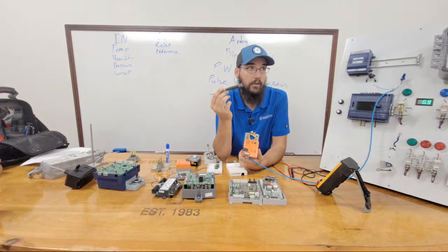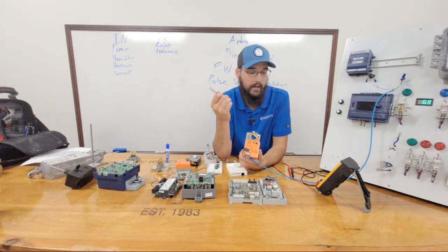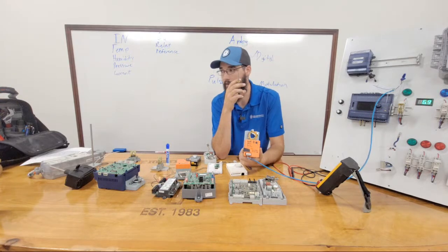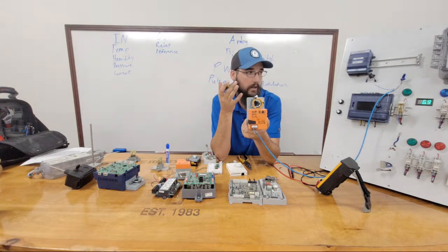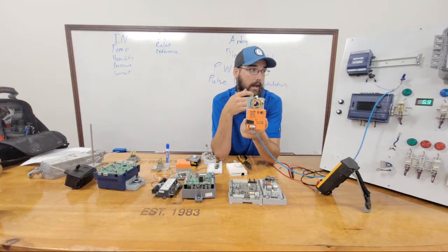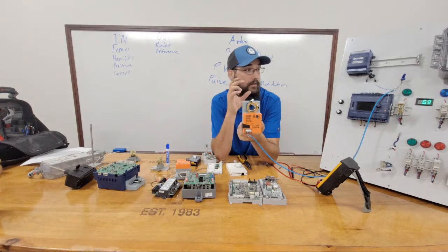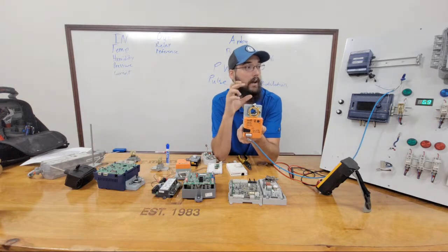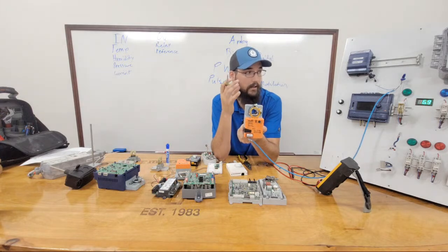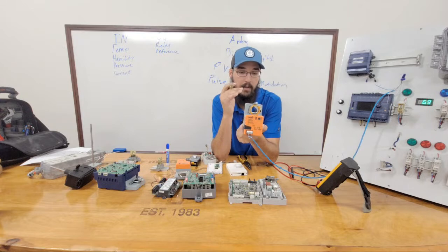So those are terms that date back to the pneumatics days. If you ever got into pneumatics or did anything on that end of the spectrum, you knew what reverse acting or RA and DA are. So if you ever walk up to a system and you see something that's got stamped on it RA or DA, that's exactly what that's referencing. It is a reverse acting or direct acting. So keep that in mind.